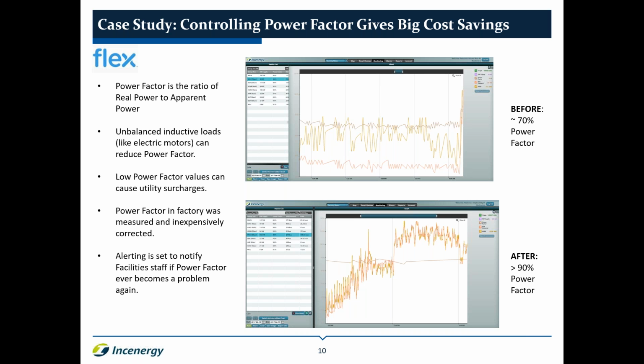And oftentimes, depending on the type of load, like an inductive load, and inductive loads are things like motors, anything that has electromagnets in it where the coil is consuming the power, that will cause the real power to be less in relation to the apparent power, which will give you a lower power factor. And in cases where we have a lower power factor, such as this example on the top here, I'm looking at the line where the power factor is less than 70%. Many utilities will assess charges at about 85% power factor. So if your power factor falls below about 85%, you will receive surcharges on your bill. These surcharges can be very substantial.